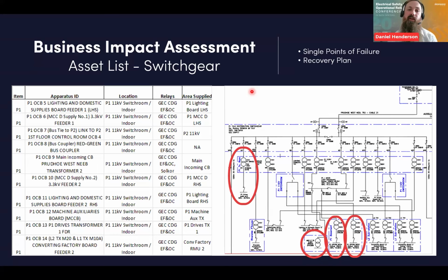As an example, in my experience at one production facility where I was the responsible person for the network, in the event of a power outage, a lot of that production was heavy steam use - steam going into rotating pressure vessels and drums. In the event of a power outage, the motor that drove that rotating pressure vessel couldn't rotate anymore. So after a period the steam cut off anyway, but it could cool down, and that cold condensate could then cause the pressure vessel to rupture, leading to a safety related incident, especially for anyone in that vicinity - it would have some impact.